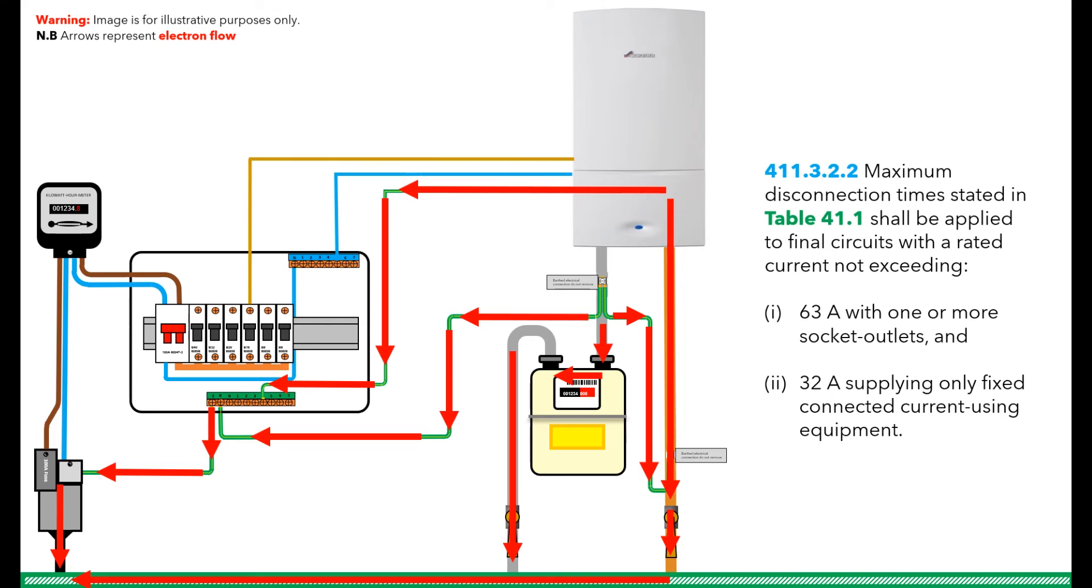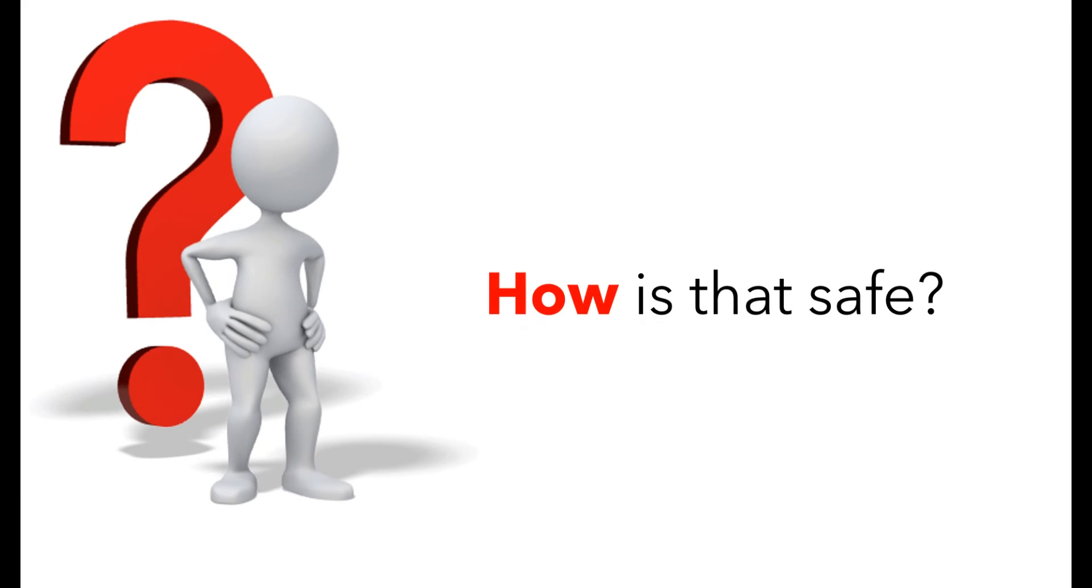Regulation 411.3.2.2 gives guidance on the maximum disconnection times and refers to table 41.1 in BS 7671. Think about that for a second. We are going to intentionally allow all the metal work to become live. So how is that even safe?